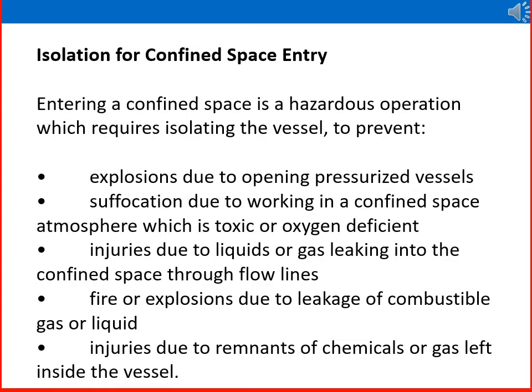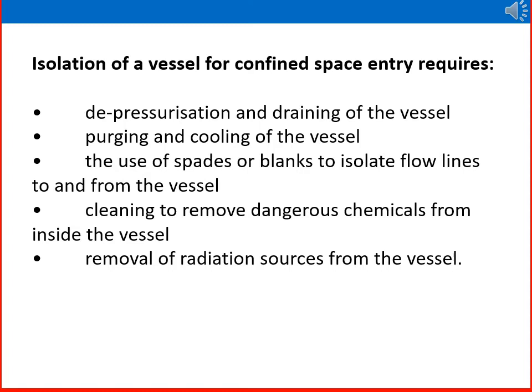Entering a confined space is a hazardous operation which requires isolating the vessel to prevent: explosions due to opening pressurized vessels; suffocation due to working in a confined space atmosphere that is toxic or oxygen deficient; injuries due to liquids or gas leaking into the confined space through flow lines; fire or explosions due to leakage of combustible gas or liquid; and injuries due to remnants of chemicals or gas left inside the vessel. Isolation of a vessel for confined space entry requires: depressurization and draining of the vessel; purging and cooling of the vessel; use of spades or blanks to isolate flow lines; cleaning to remove dangerous chemicals; and removal of radiation sources from the vessel.